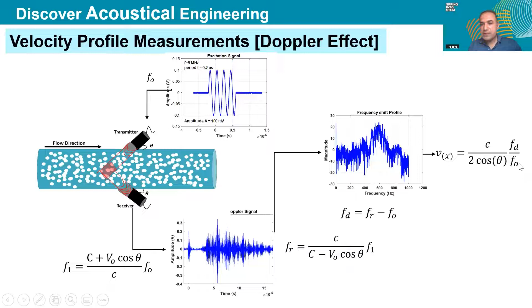To calculate the Doppler frequency, you detect the initial frequency of the sound wave you send by this equation, and use the fast Fourier transform to extract the frequency spectrum. When you have the Doppler frequency, you feed it to this equation to calculate the velocity profile. C is the sound speed in the mixture here, theta is the inclination angle of the transducers, F naught is the initial frequency you send, and FD is the Doppler frequency.